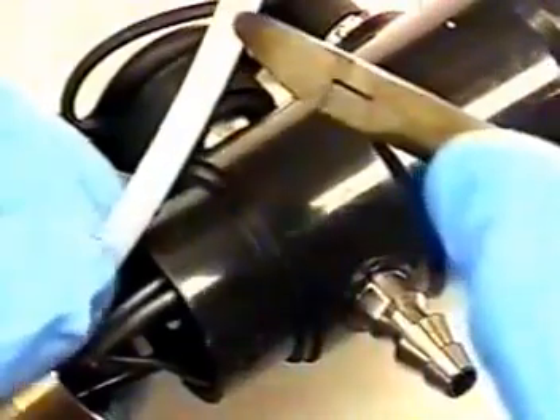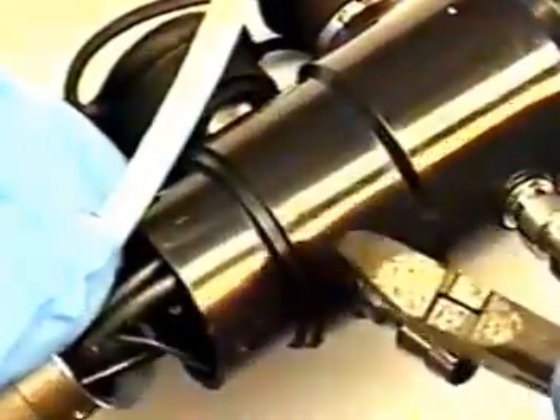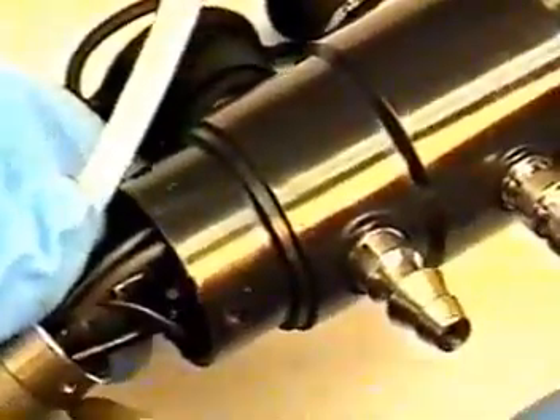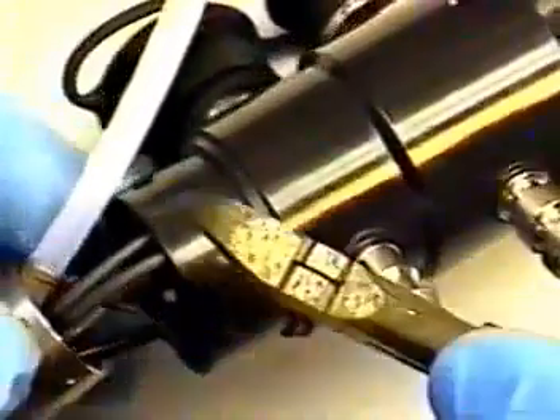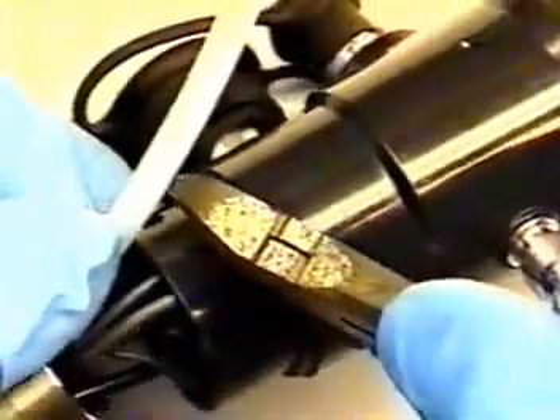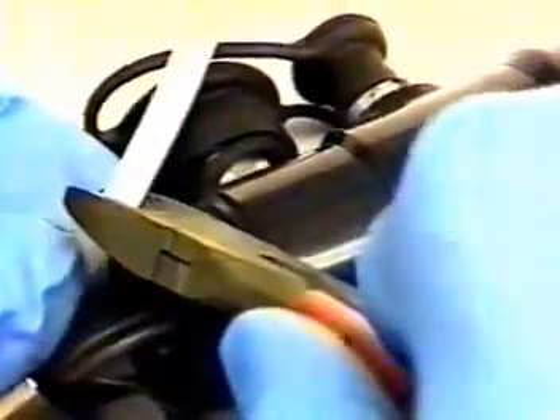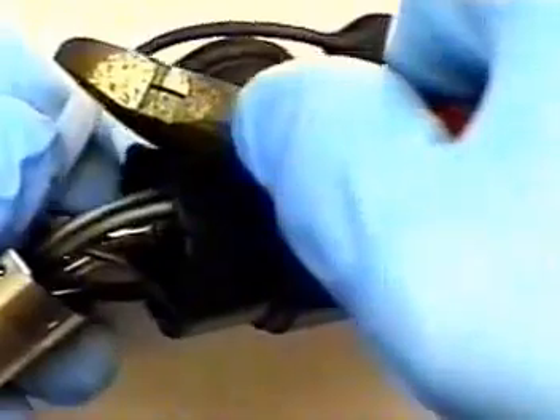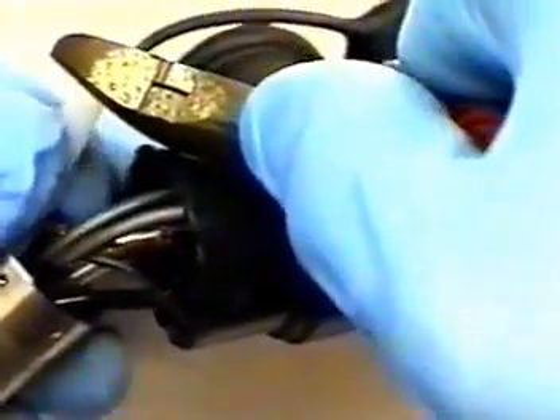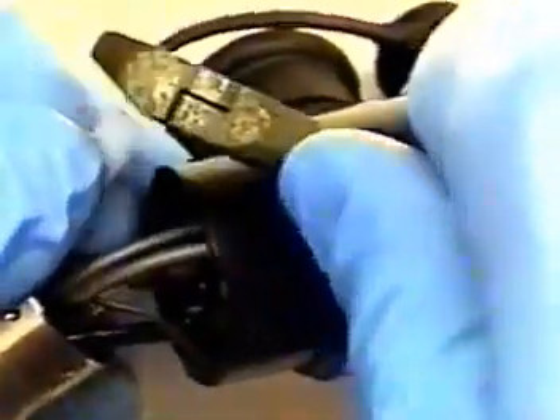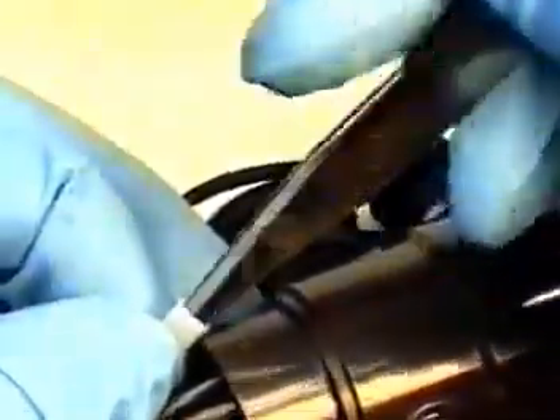Be careful not to cut too short or too long. This will not allow the connector to fit back on the umbilical cord properly. So again, approximate cutting to meet the suction port. Use a pair of tweezers and round suction tube.